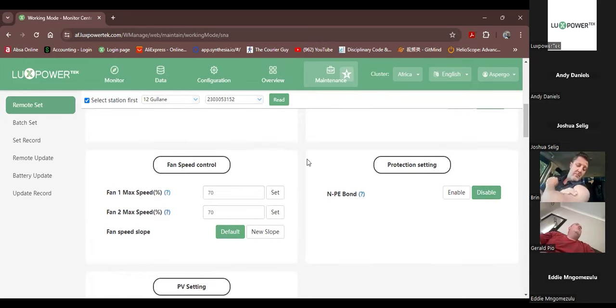Right, so here we have a very cool feature that's also been added now. It's the neutral and potential earth bond, or the bonding. All right, so you can enable it, but remember that the older versions of the SNAs do not come with the neutral earth bonding relay installed. Only the new 6 kilowatt SNAs and the newer machines that will be arriving after the current stock has been depleted will come with the bonding relay installed. So there's no need to fit the jumper any longer between your output neutral and the potential earth. You can simply enable it here.